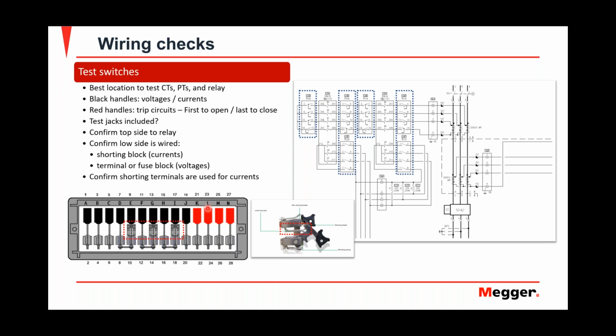Why? Because let's say you start opening your voltages and your currents. Now that relay sees, let's say you only pull 1 voltage. Now your relay is going to see an under voltage condition on phase A, and it's going to trip. But guess what? You left your trip circuits closed, so it's going to trip the breaker when you did not intend to. So the red switches go out first to open, but the last ones to close, especially on electromechanical relays. That's something that you have to keep in mind.